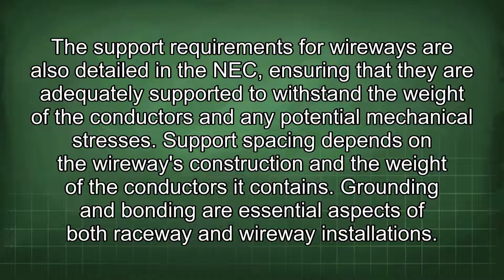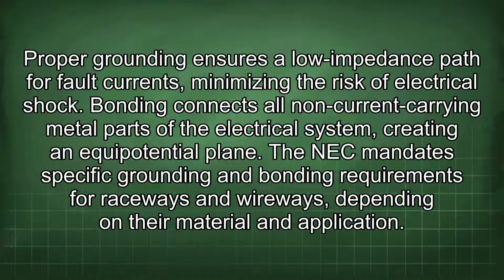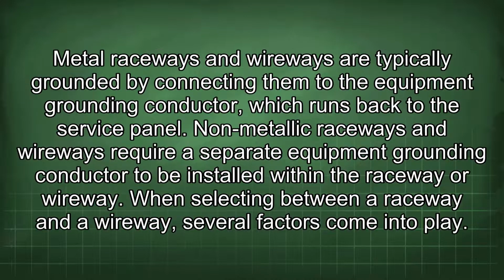Grounding and bonding are essential aspects of both raceway and wireway installations. Proper grounding ensures a low impedance path for fault currents, minimizing the risk of electrical shock. Bonding connects all non-current carrying metal parts of the electrical system, creating an equipotential plane. The NEC mandates specific grounding and bonding requirements for raceways and wireways, depending on their material and application. Metal raceways and wireways are typically grounded by connecting them to the equipment grounding conductor, which runs back to the service panel. Non-metallic raceways and wireways require a separate equipment grounding conductor to be installed within the raceway or wireway.